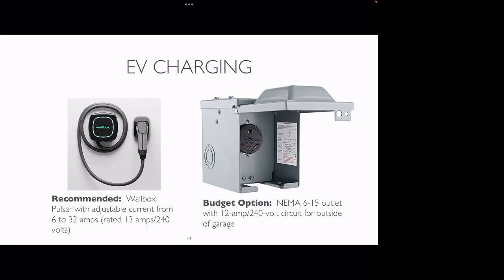So we find one of the biggest mistakes people make when they're electrifying is if the first thing they do is get an EV and install a level 2 EV charger, they get a huge charger, like a 50 amp car charger. This is completely not necessary unless you drive like 200 to 300 miles a day. You don't need a charger that size. If, like me, you generally need maybe max 100 miles of charge a night, then a 15 amp 240 volt car charger is plenty. So this Wallbox Pulsar can be adjusted by the electrician to help you stay within your panel capacity.